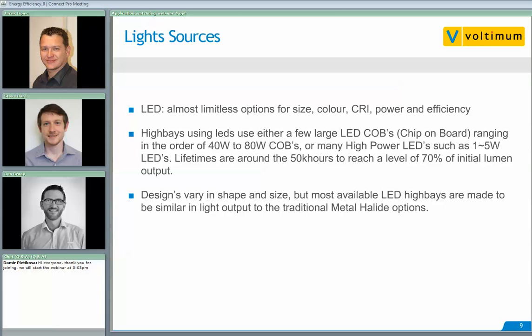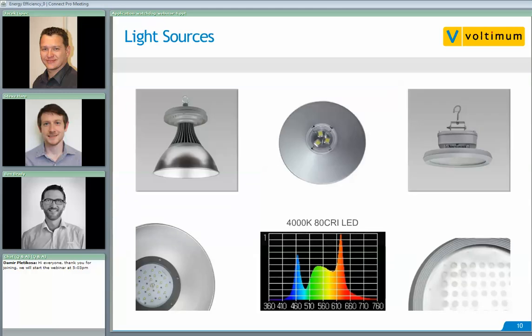LEDs don't tend to fail as other lamp sources do — they tend to just degrade in lumen output, so catastrophic failure is relatively unlikely. Most available LED high bays are made to be similar in light output to traditional metal halide options. Some designs mimic the look of traditional metal halide high bays, while others concentrate on the requirements of the luminaire — the form factor and a large enough heat sink to efficiently cool the LEDs. A typical 4000K LED offers more even color rendering than metal halide, allowing better color representation in manufacturing or warehousing applications.